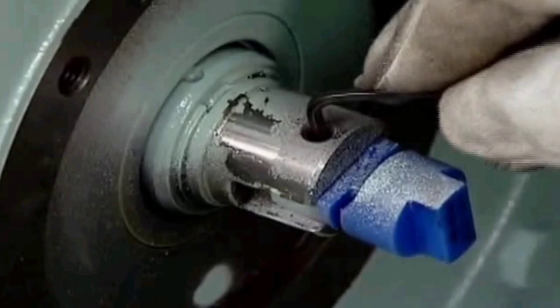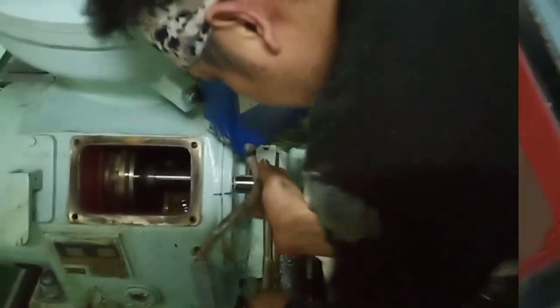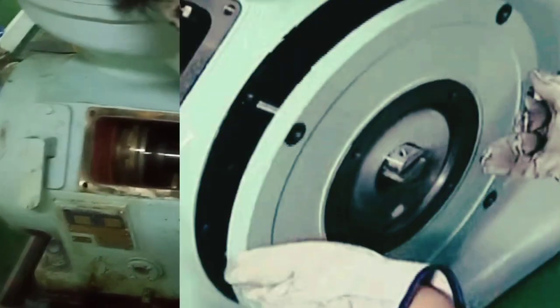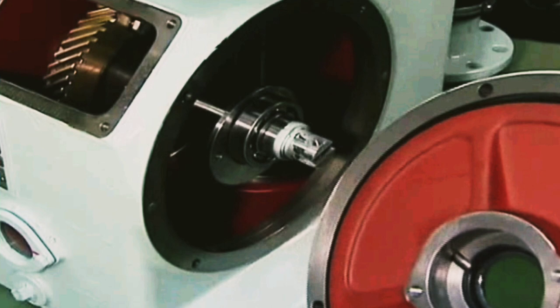Loosen the screw of the safety joint attached and remove the safety joint and screw. Then, remove the two bolts that fasten the bearing retainer. Remove the four bolts that fasten the large bearing housing and screw with two push bolts in the groove to loosen the large bearing housing and remove the bearing housing.